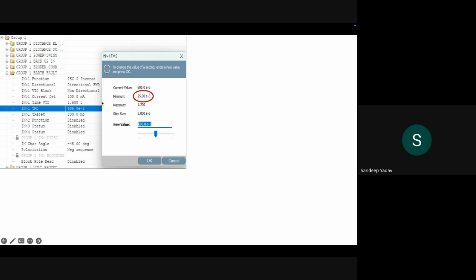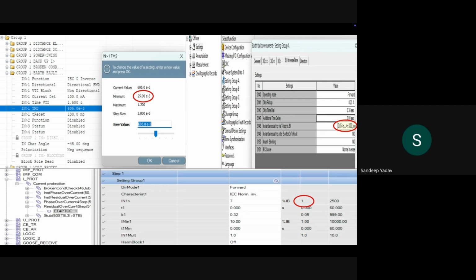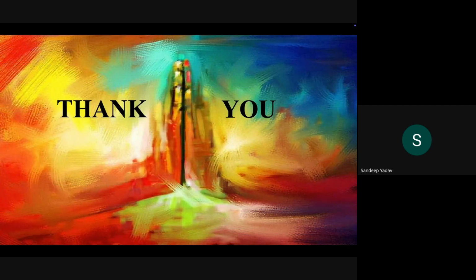Because of this problem, it is very difficult to set these earth fault relays or the backup earth fault relays in case of an RE generator end. So this is one of the challenges. What we do is that we keep the minimum fault current which is available on the relay. In this case, this is 0.025, and we just leave it at that. Okay. So thank you so much. That was all from my side.